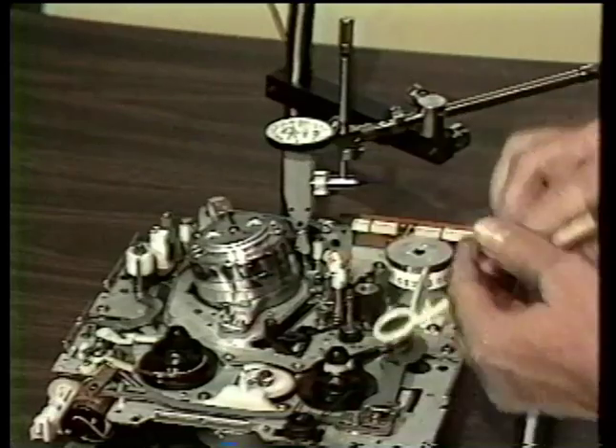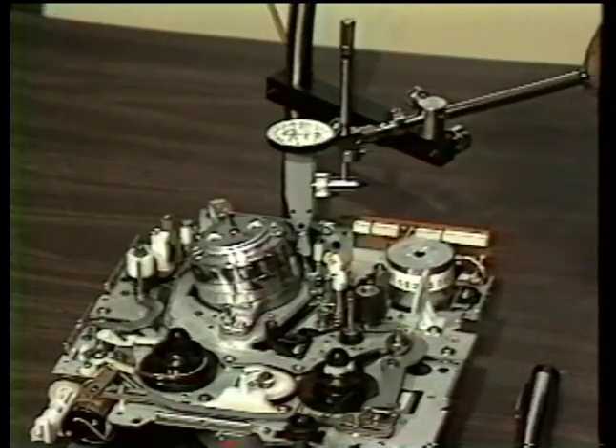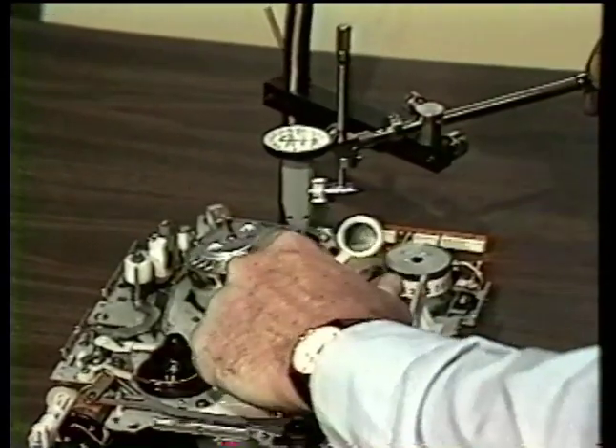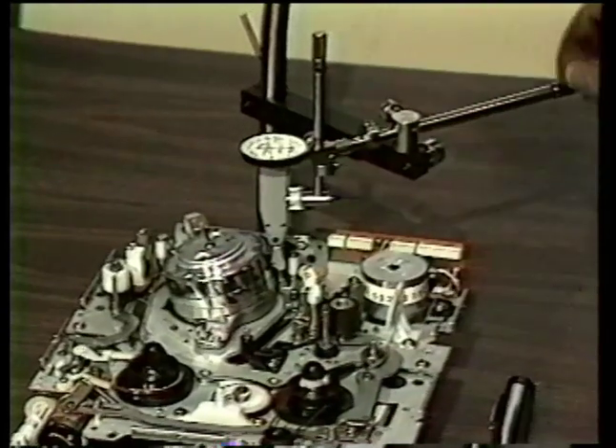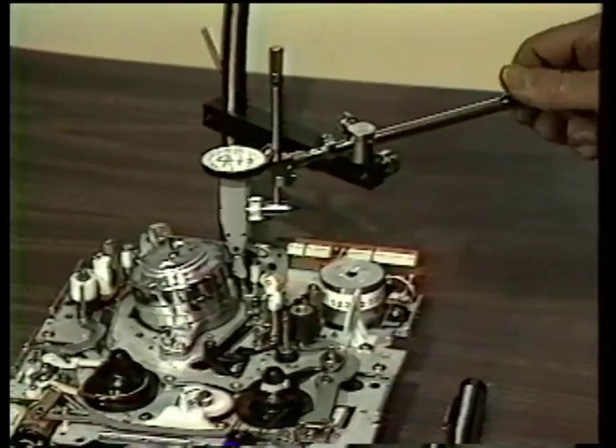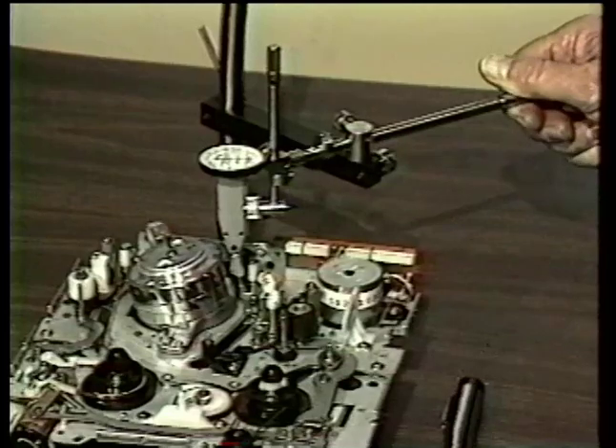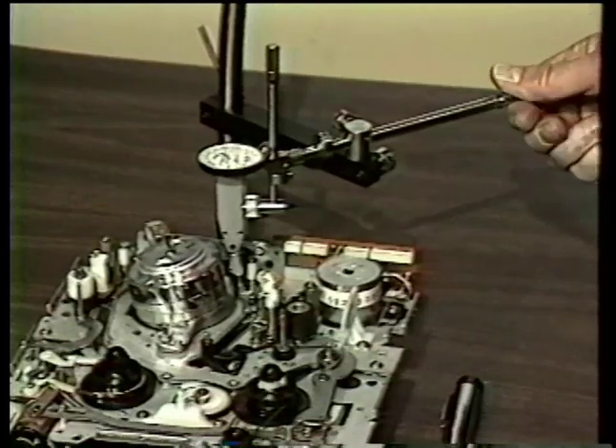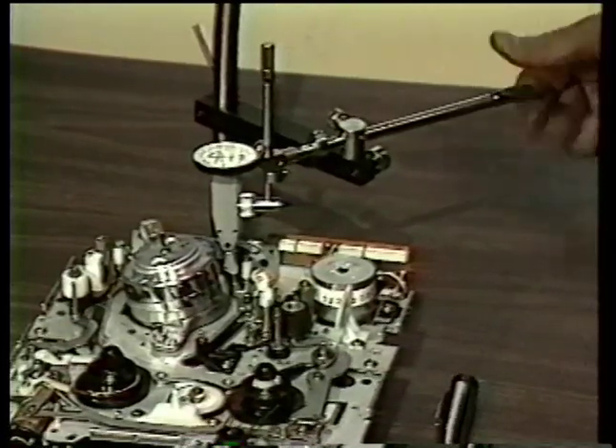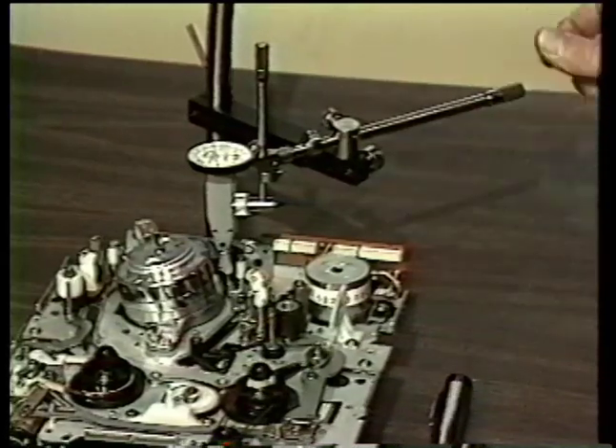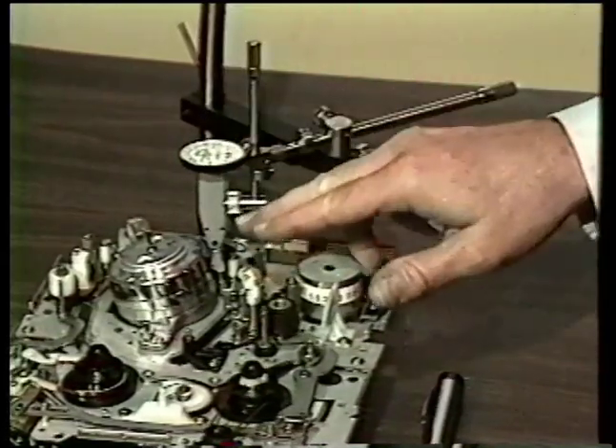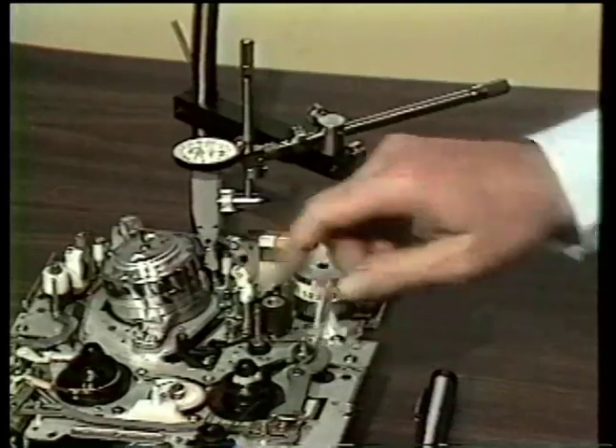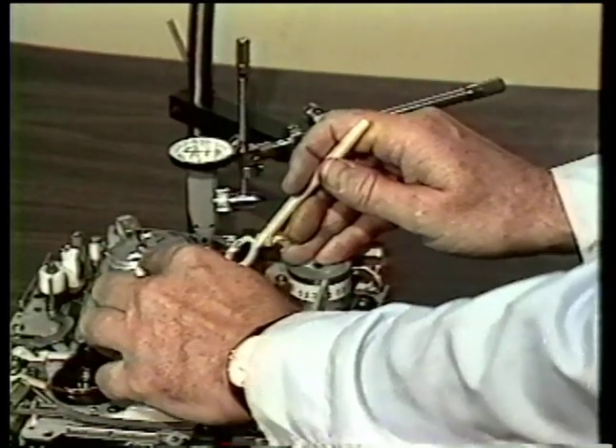Right now, with the positioner, I'm going to come over without the head against it. The head is back away. Bring this over and actually do an alignment until the pointer moves. You see the pointer moving there. And then back it away about a half a turn. This provides up and down motion. We don't want to do up and down motion with this tip against a head drum, or with a head tip.